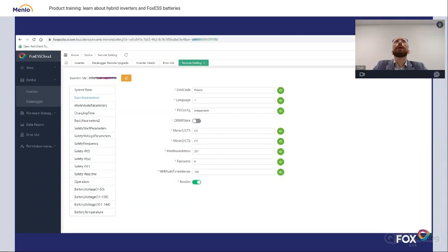So let's check, because basic parameters are the most important to properly set the unit the first time to engage and not to do a mishap there. You must properly set the grid code for your local grid, for the country in which you install the device, and change the language accordingly. Right now, I believe English is the most used on those devices, but of course we may provide a translation in any other language, so this is not a problem.